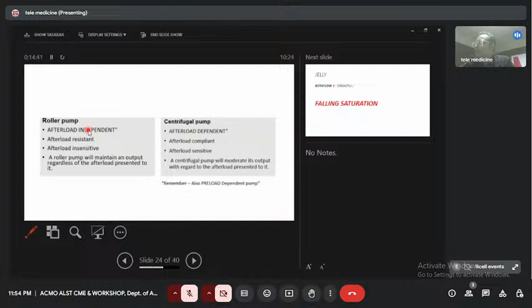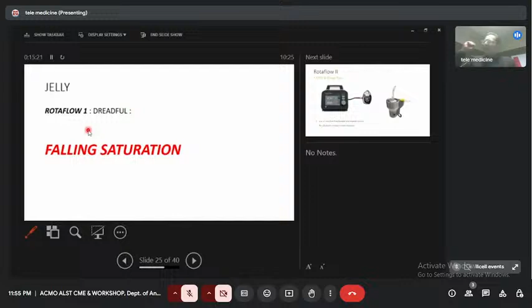So the next important component is the jelly, because in a few centers, if you have a Rotaflow 1 and you see the saturation is falling, the pump is not functioning because the jelly is exhausted. At the console, the jelly is exhausted under the pump head. So the jelly is again a very important component if you are using Rotaflow. The falling saturation, pump not working, this is a magnetic console like USG, ultrasound probe. The jelly is not functional, it won't sense at what speed the blood is moving.